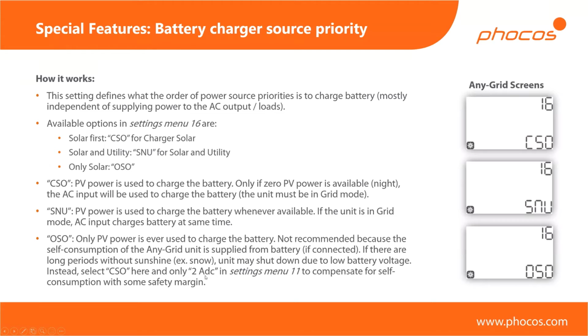But then you can use a very small charging current, so only 2 amps on the battery side. So that's like around about 98 watts, roughly, that you're allowed to charge from the grid. And what that will do is it will offset the self-consumption of the AnyGrid, and at the same time, a little bit more to just like almost trickle charge your battery with 1 amp.